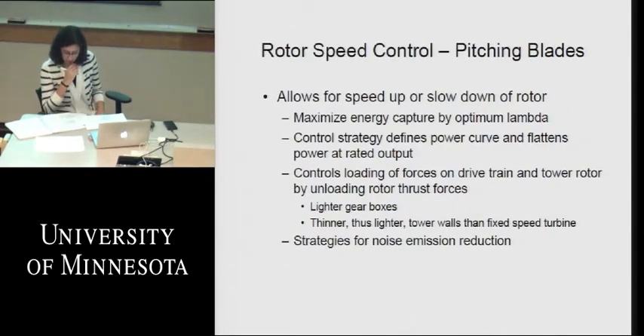So again, pitching the blades allows us to slow down or speed up the rotor, depending on how we want to control, maybe for power control, maybe for sound control, like we say. But ideally, it's to optimize the energy capture by optimizing our lambda, the tip speed ratio. Like I say, it's also a control strategy for the power curve, as I said earlier, but also we want to flatten out the power when we reach rated conditions so we don't get that overshoot of power like we would with the Type 1.